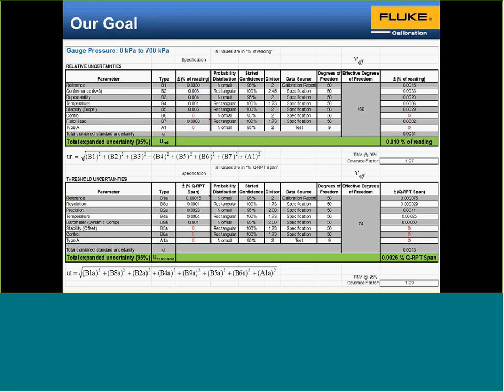So this is pretty much our goal. What you want to come up with is an itemized budget of all uncertainty parameters, the type of distribution, the type of uncertainty they're presenting, their interval, and any information that helps somebody look at this and see what it is. Notice I have parameter type, percent of reading, percent of full scale. I have where I'm getting the uncertainty source from, whether it's a calibration report, a specification, or a test. I list the degrees of freedom, and I list everything at one standard uncertainty, for the type of uncertainty we're talking about, either relative or absolute. Then our goal is to report at 95% confidence. We'll talk about each one of these contributors as we go through the presentation.